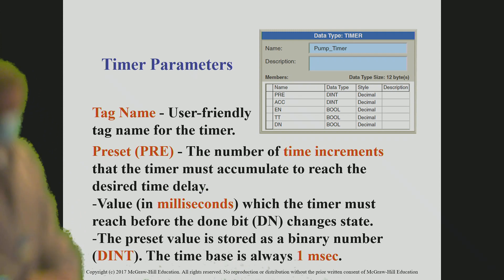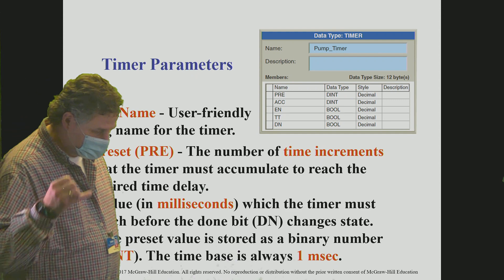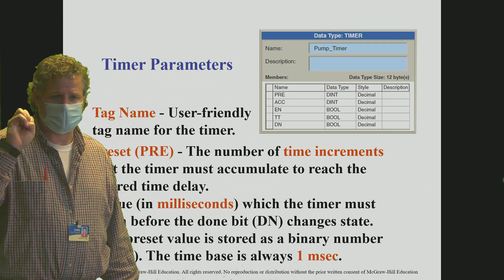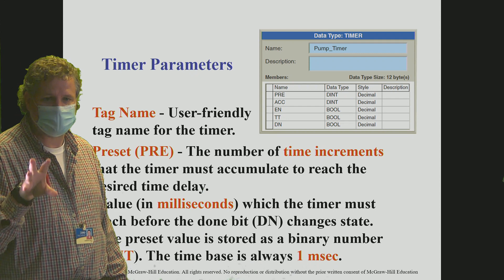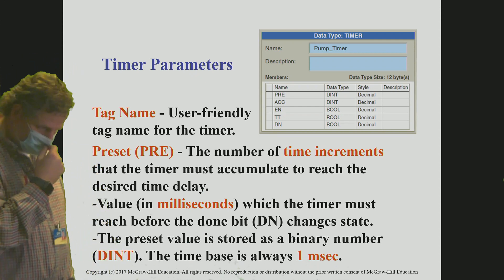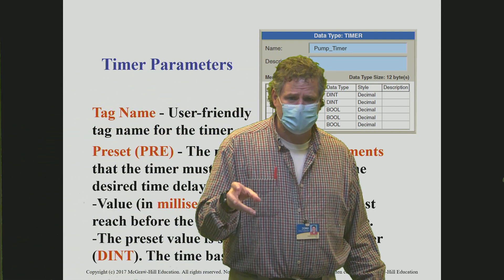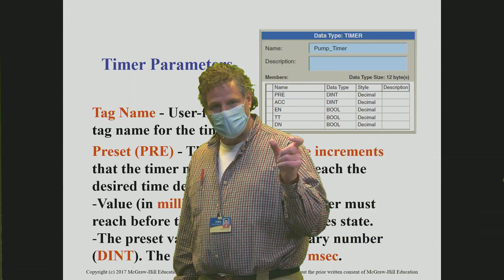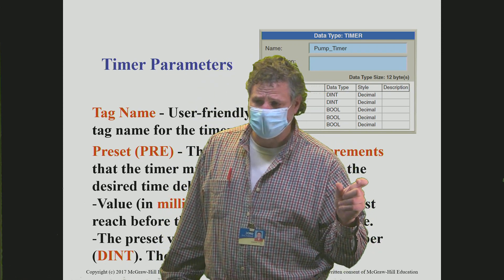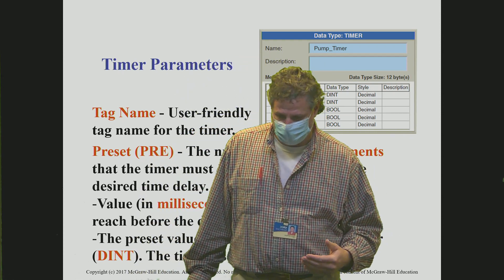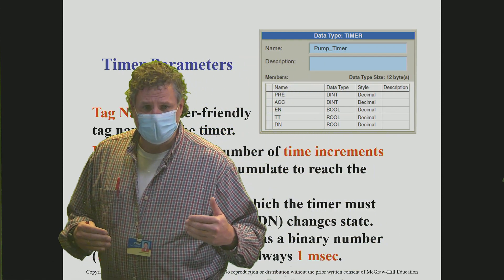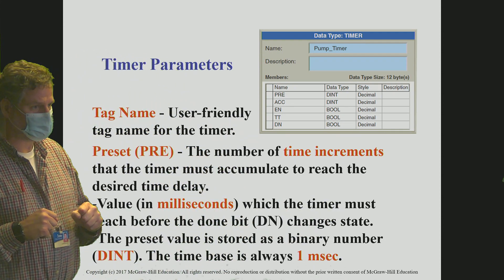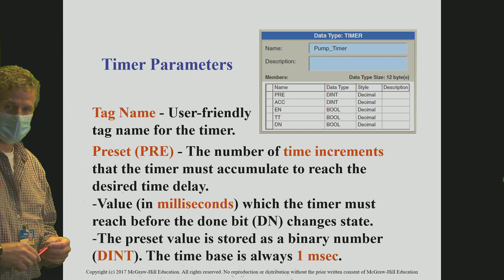Regarding the tag name — the key point about the tag name in a timer application is that the data type has to be defined as a timer. Why is that important? Because if you put a double integer data type in a timer, it's only going to recognize one word. It's not going to time — it's going to give you errors saying wrong data type for this instruction. We've got to make sure when we're using timers that we set that data type to timer. This is a critical path.